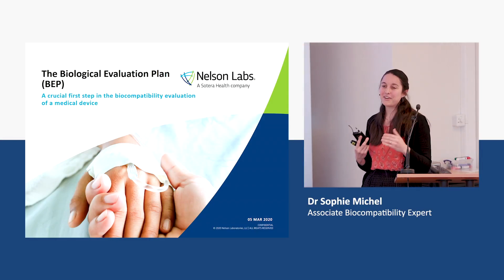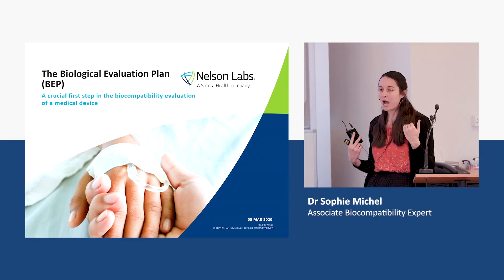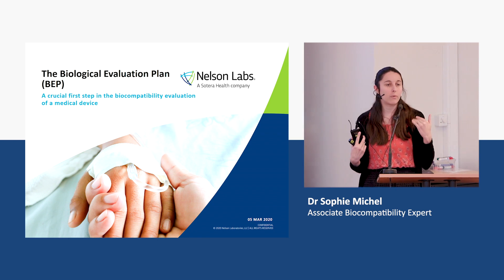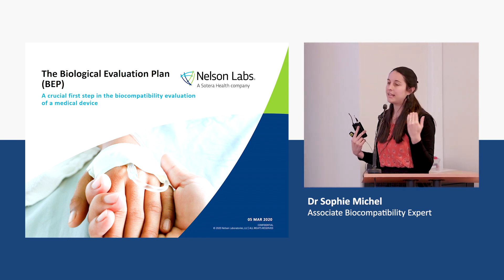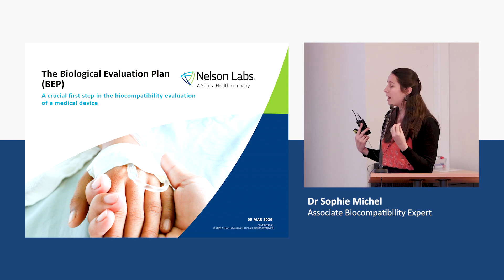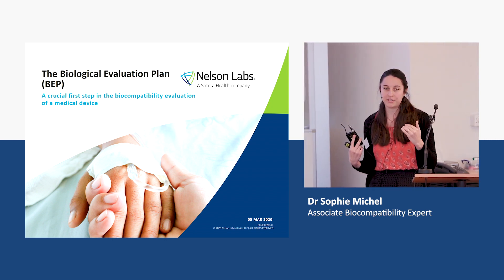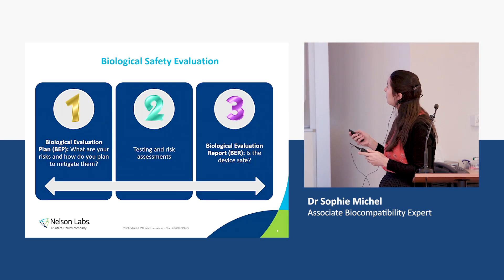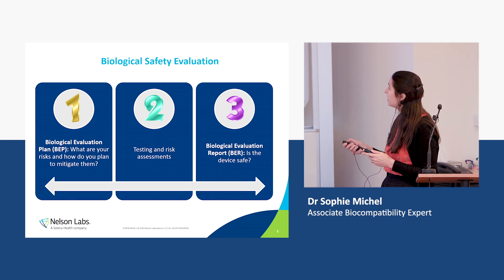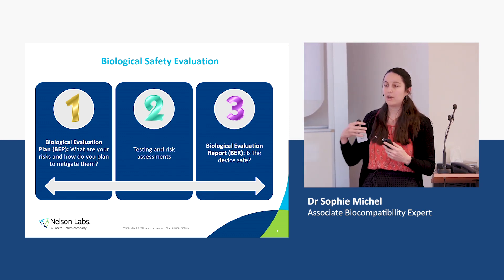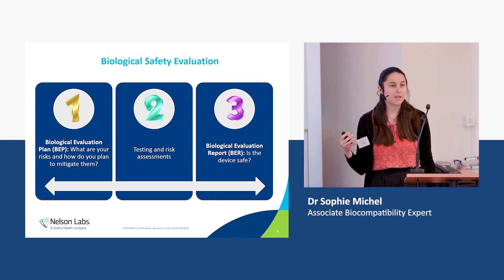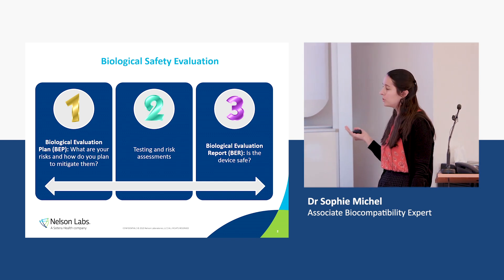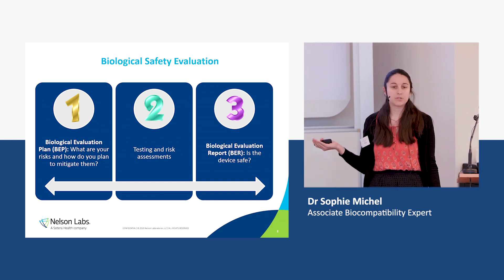So what is a BEP? It's actually a document in which you are going to outline which biological risks can occur to the patient or to the healthcare provider when using your medical device, and in which you're also going to explain how you're going to address or mitigate these biological risks. In your overall biocompatibility strategy, we are just here — it's your first primary stage before you actually proceed with any testing, and before you evaluate the results of this testing to conclude on whether or not your product is safe to the patient.